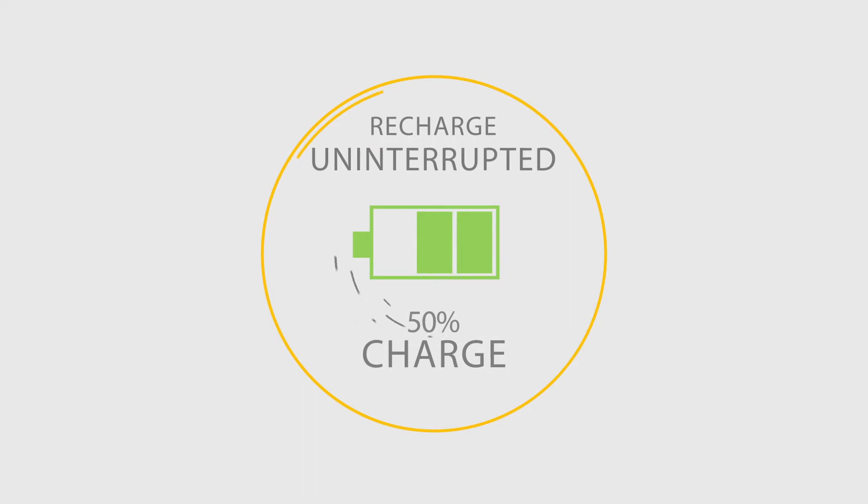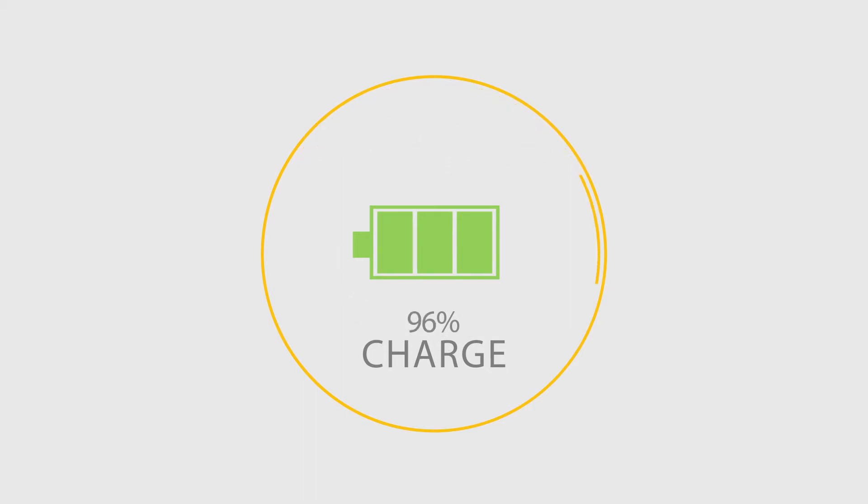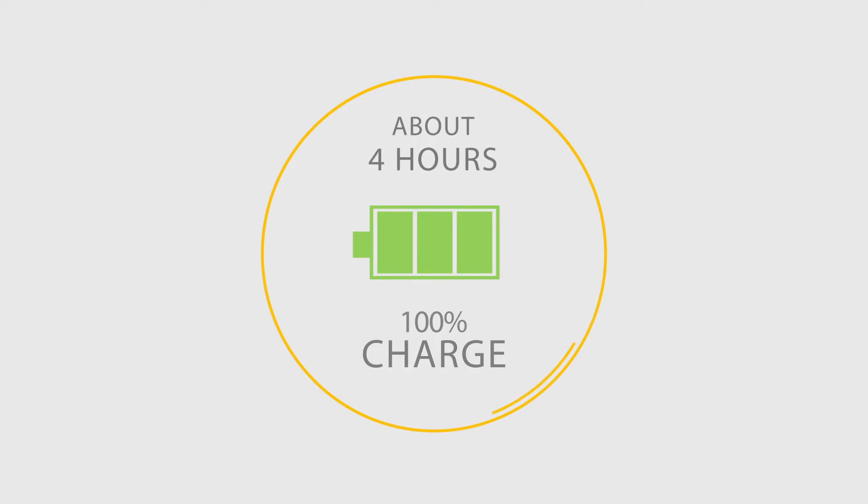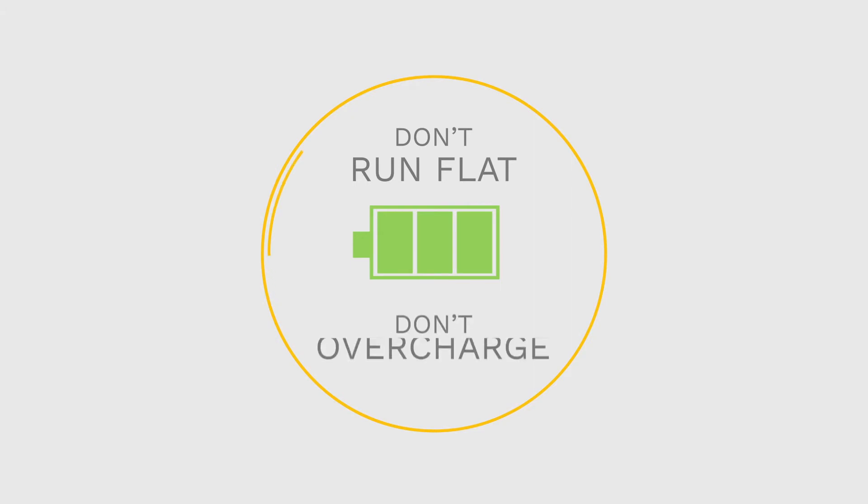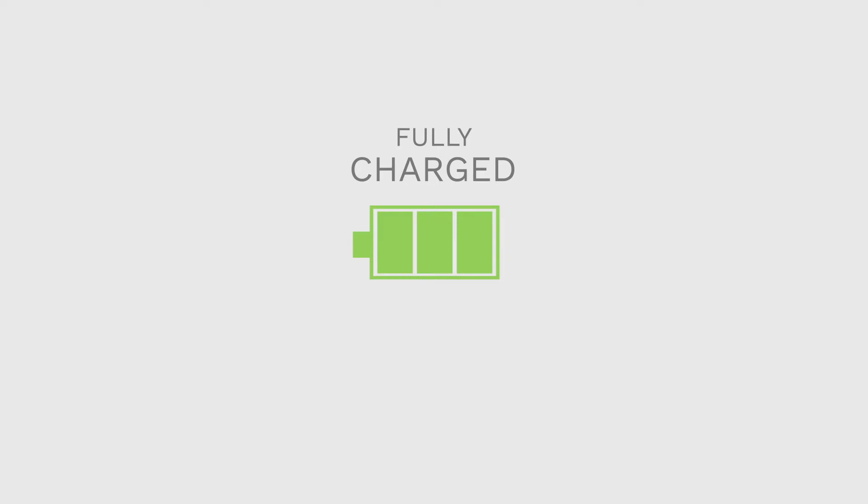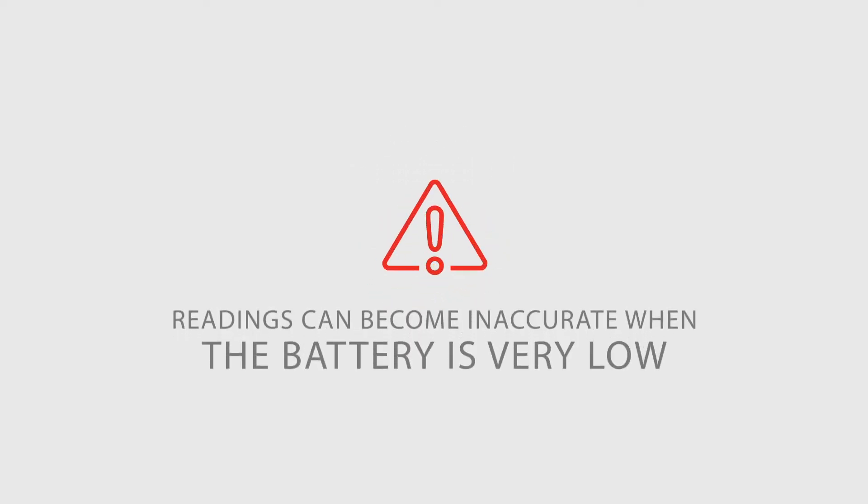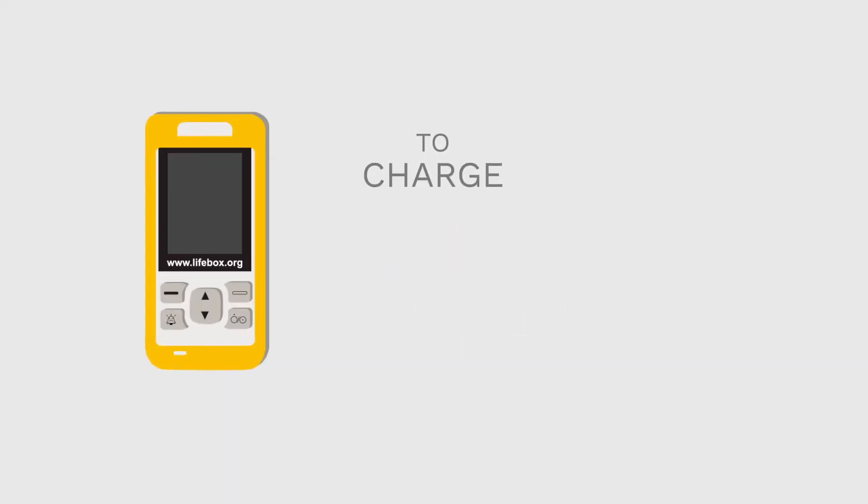Then, recharge the battery, uninterrupted, until it is fully charged. This will take about 4 hours. After that, it's better for the health of your battery not to let it go completely flat and not to overcharge it. This is a bit like your mobile phone. When it's fully charged, this battery should run for 12 to 16 hours. Note that readings can become inaccurate when the battery is very low.